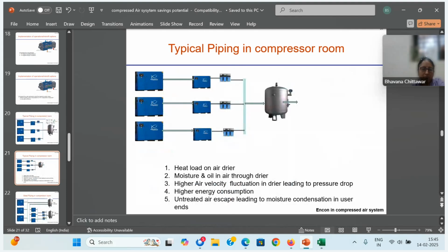There is a higher heat load on the air dryer. Moisture and oil in the air go through the dryer. High velocity or fluctuation in the dryer. Higher velocity across the dryer and fluctuation, as the compressor loads and unloads. During loading, velocity will be more; unloaded, no airflow. Higher energy consumption due to pressure drop. Untreated air sometimes escapes through the air dryer, so it will go and condense at the user points.